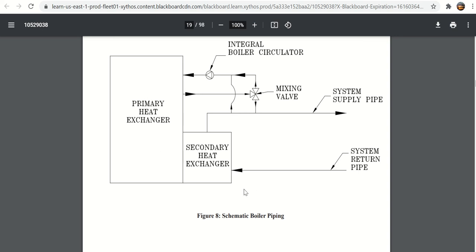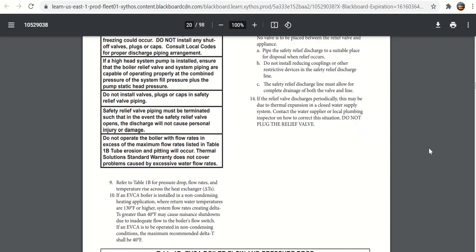That's an important thing. Any condensing has to happen in the secondary heat exchanger because that's where the drain pan is. You can't have condensing in there, so they try and keep the water temperature right here at probably 125 to 130 degrees minimum, and they do that by either recirculating hot water through the mixing valve, or if it's not recirculating, it's taking some of the water off the secondary heat exchanger and going in.